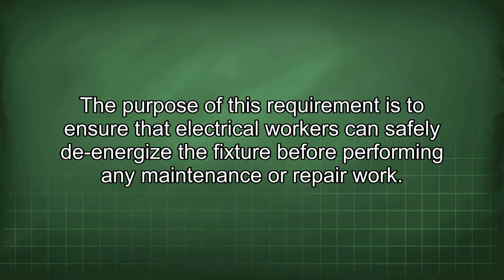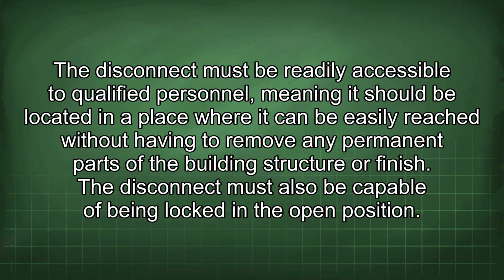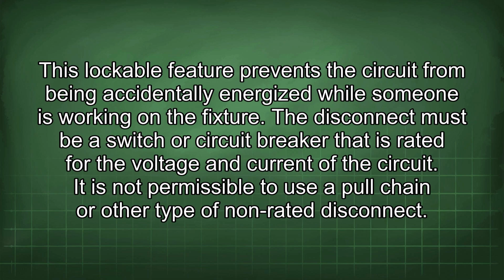or repair work. The disconnect must be readily accessible to qualified personnel, meaning it should be located in a place where it can be easily reached without having to remove any permanent parts of the building structure or finish. The disconnect must also be capable of being locked in the open position. This lockable feature prevents the circuit from being accidentally energized while someone is working on the fixture.